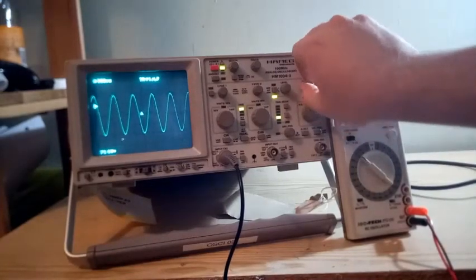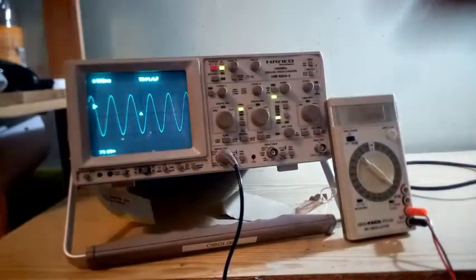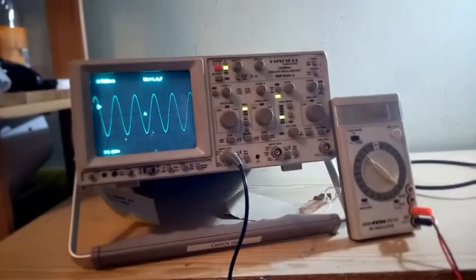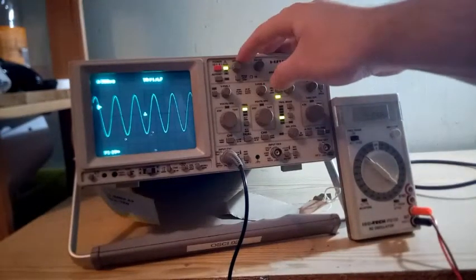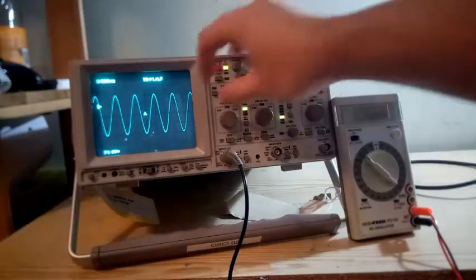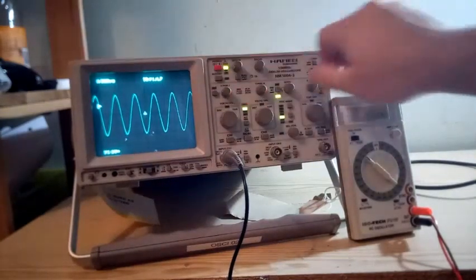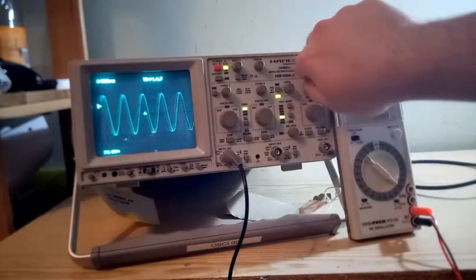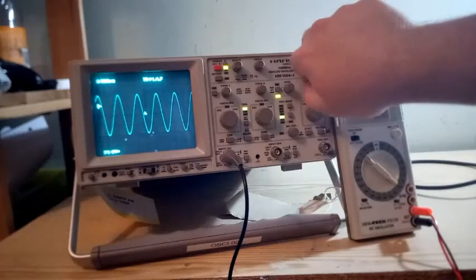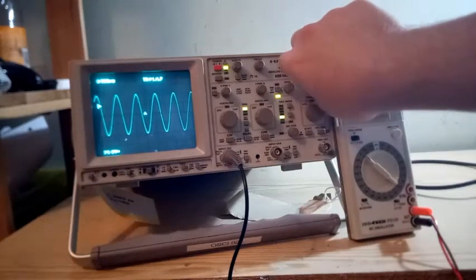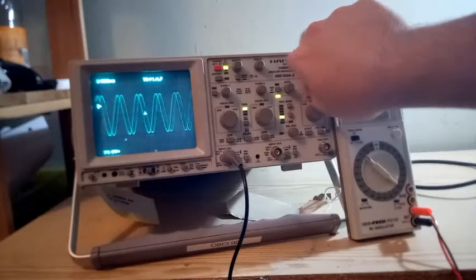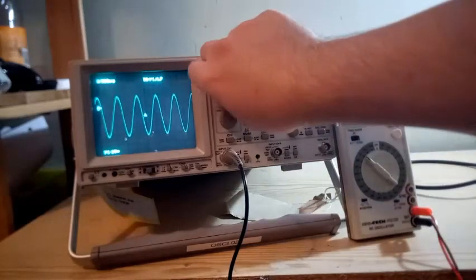You can put marks on the screen, and they're permanent, so I try and keep the intensity down. The other ones I've used are Y position and X position. As you can see, X position moves the capture of your wave from side to side, Y position up and down.